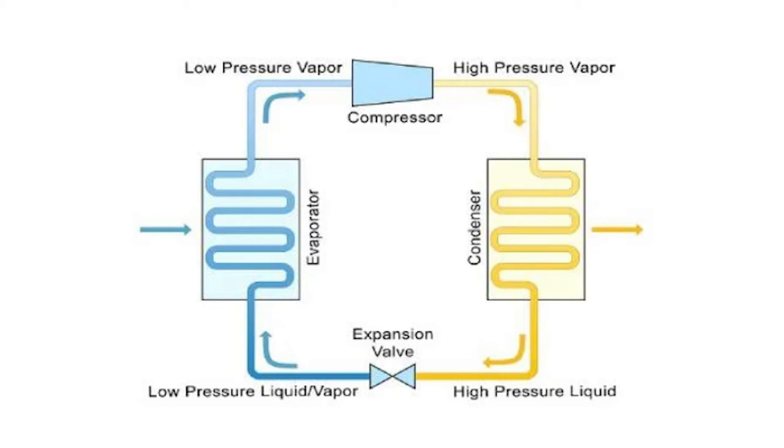The compressor raises the pressure of the refrigerant before it enters the condenser, and thereby raises its temperature high enough to allow for the heat exchange necessary to change its state. The compressor therefore serves the dual purpose of raising the pressure and temperature of the refrigerant entering the condenser, as well as circulating the refrigerant through the system.